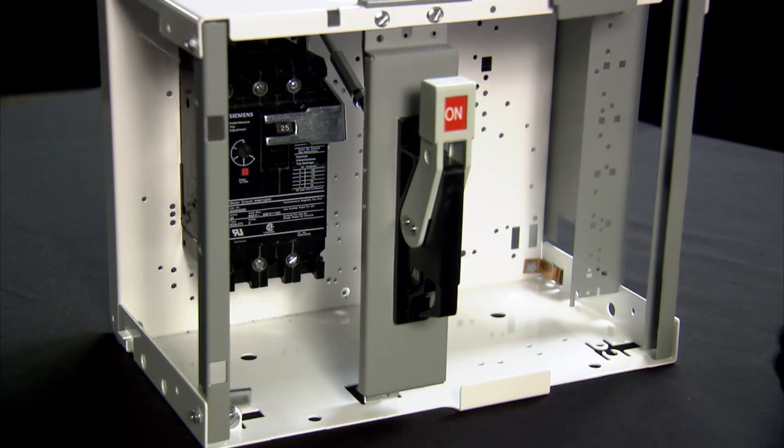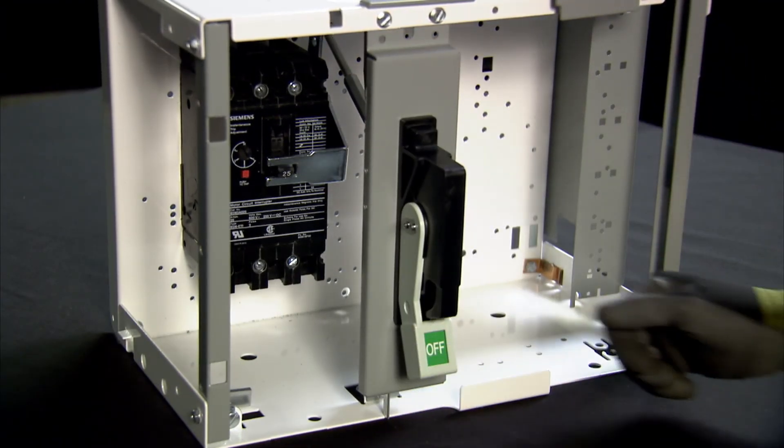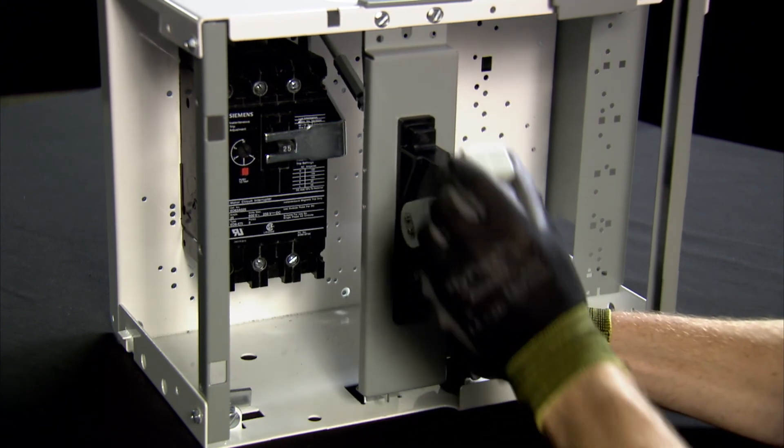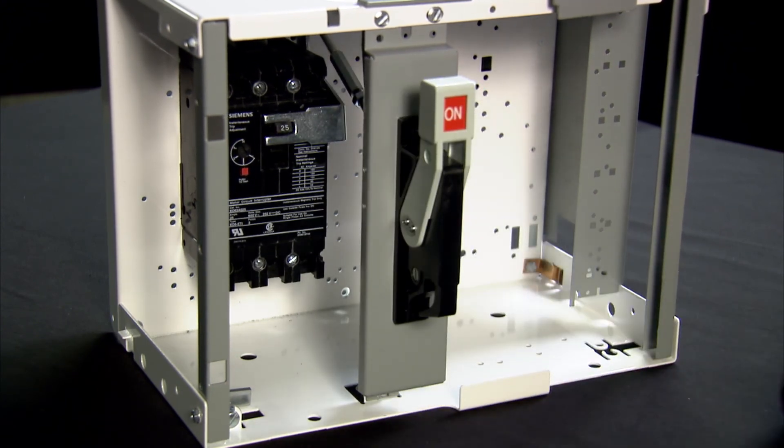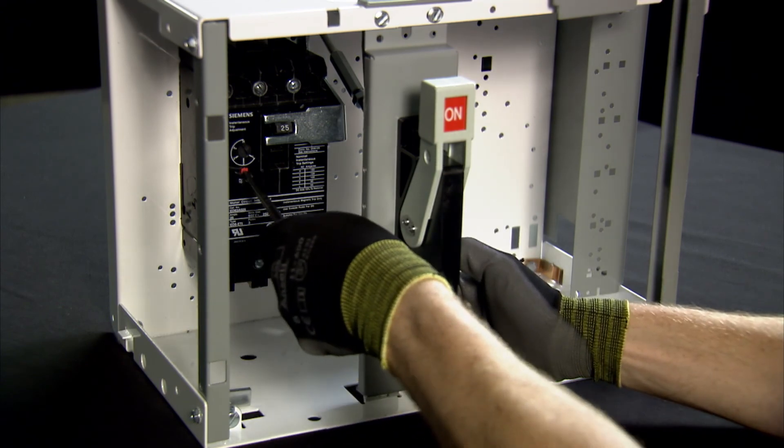This is how a properly functioning handle should behave. The handle door interlock lever must be held down while testing the trip function of the breaker. If the lever is not held down, the handle will not fall into the trip position properly.